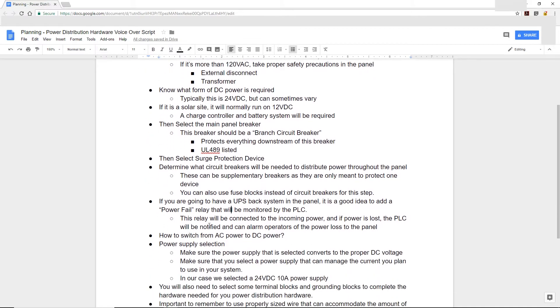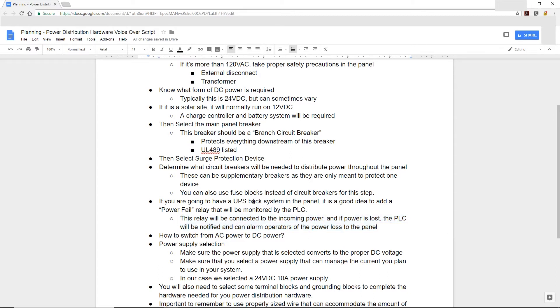The next thing we want to look at is whether we're going to use a UPS system — an uninterruptible power supply — for our control panel. If we are going to use a UPS, we also might want to look at using something called a power fail relay. The purpose of the power fail relay is that our incoming power is connected to this relay, which monitors the utility or incoming power to our panel. When that power fails or goes off, it sends a signal to the PLC, which can then alarm any operators in the area of a power loss so they can address it as needed. A power fail relay is a great option when using a UPS backup system.